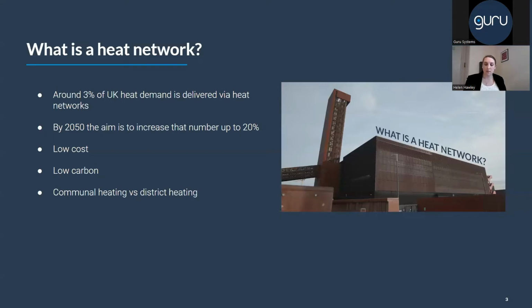Also, for the system, you tend to have a large delta T. So on the supply side of the network, or the primary side of the network, you might supply hot water to the dwelling at 60 degrees and you want to strip all that heat out of the supply and return the water back to the plant room at 30 degrees, which means that you're using all the energy that you've put into the network. And it's this efficiency of the system design that allows you to have real carbon savings, and also because the system is so efficient in its energy usage, you save financially on running the system too.